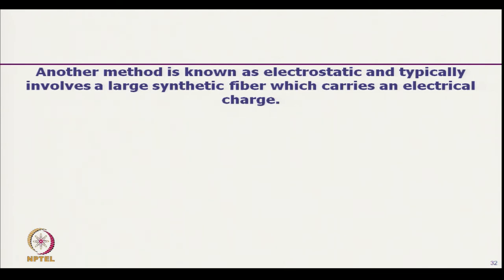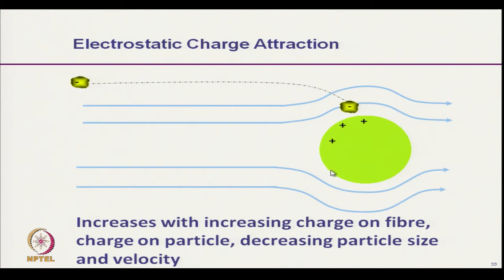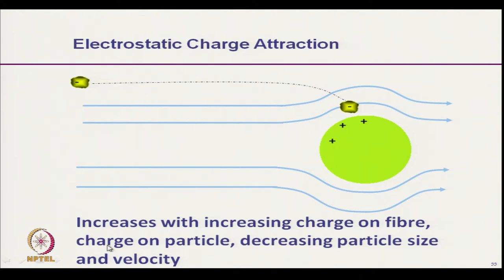Another mechanism is electrostatic charges. The fiber is charged with positive charge, while the negatively charged particle gets attracted. This effect increases with increase in charge on the fiber — higher charge attracts more particles — and also with increase in charge on the particle, decreasing particle size, and reducing velocity. The best results are achieved when the velocity of the stream is low.